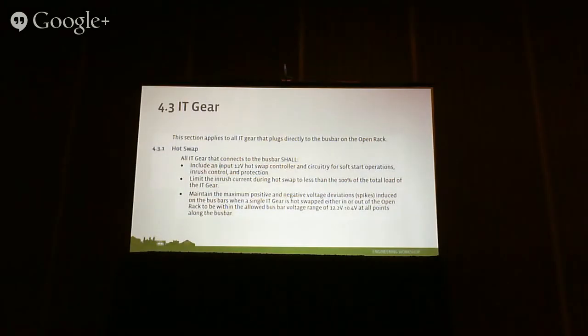Okay, so these are requirements specific to the IT gear itself. This really has nothing to do with the rack per se. This section, as it says, applies to just the IT gear that plugs directly to the bus bars. There are certain requirements that are necessary to make sure that the system as a whole plays well together. Any IT gear that does connect to the bus bar shall include a 12-volt hot swap controller and circuitry for soft start operations, inrush control and protection.